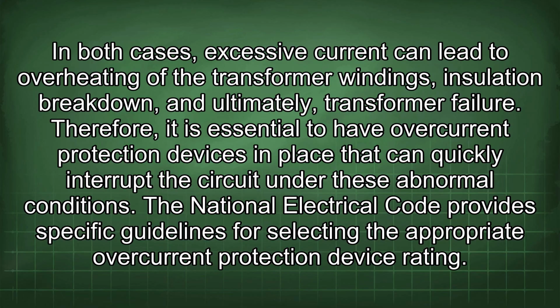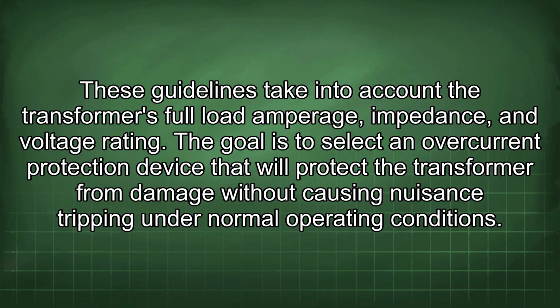Therefore, it is essential to have overcurrent protection devices in place that can quickly interrupt the circuit under these abnormal conditions. The National Electrical Code provides specific guidelines for selecting the appropriate overcurrent protection device rating. These guidelines take into account the transformer's full load amperage, impedance, and voltage rating.